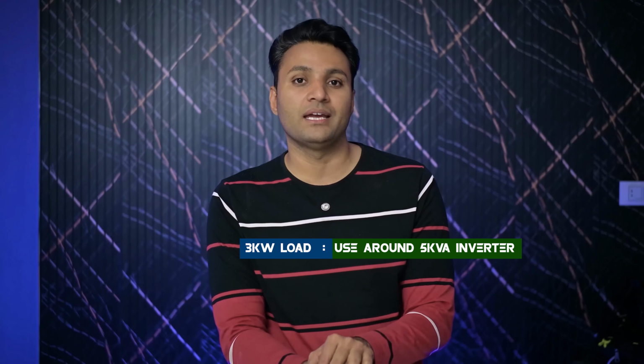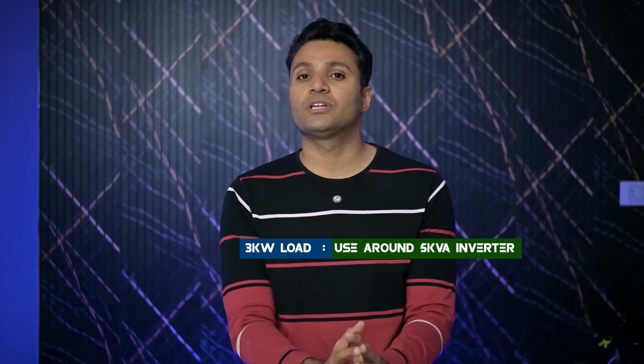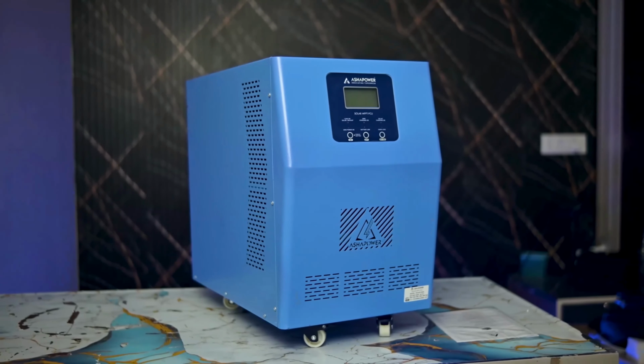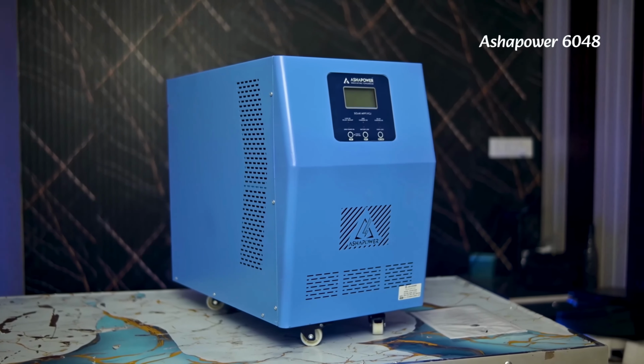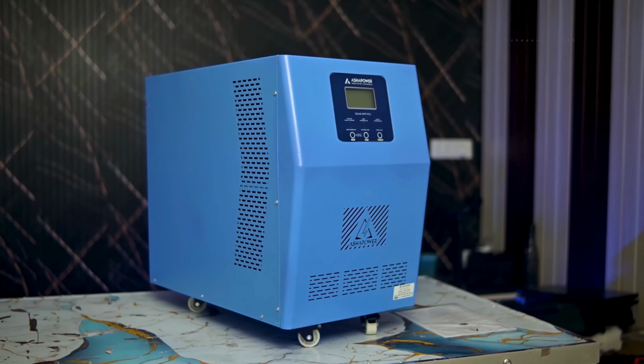Only then your load will run properly. Similarly, if you want to run a 3 kilowatt load, then in the market you usually need a 5 kVA inverter. A 5 kVA inverter is officially said to handle around 4 kilowatts load, but most company inverters can only handle around 3500 watts. Again, we tested the 6048 model from Asha Power and it could handle more than 4000 watts load because it comes with higher actual capacity.